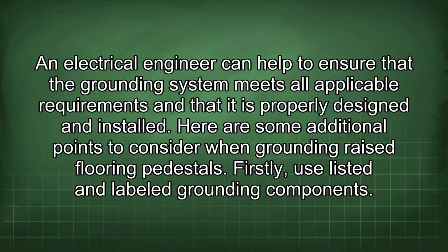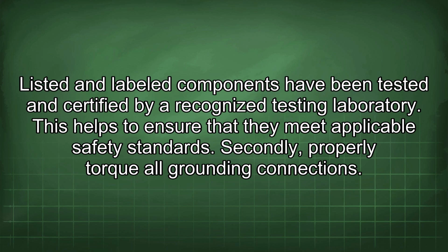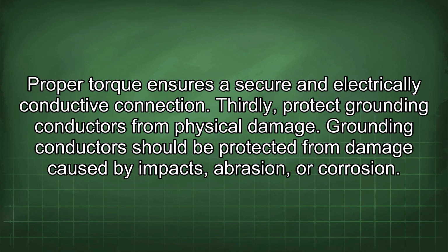Here are some additional points to consider when grounding raised flooring pedestals. Firstly, use listed and labeled grounding components. Listed and labeled components have been tested and certified by a recognized testing laboratory. This helps to ensure that they meet applicable safety standards. Secondly, properly torque all grounding connections. Proper torque ensures a secure and electrically conductive connection.